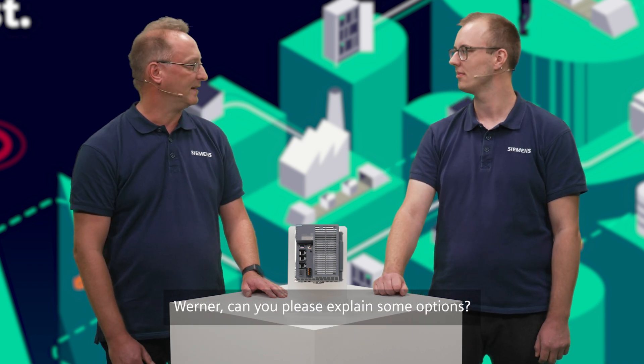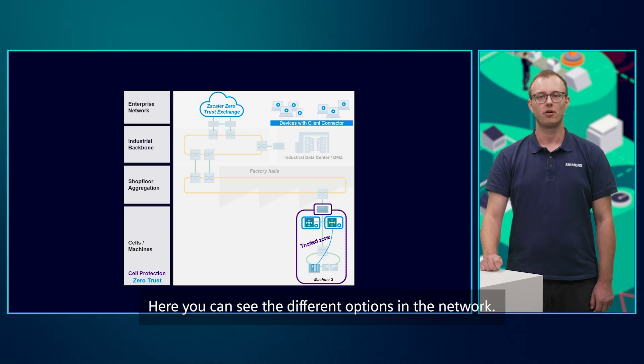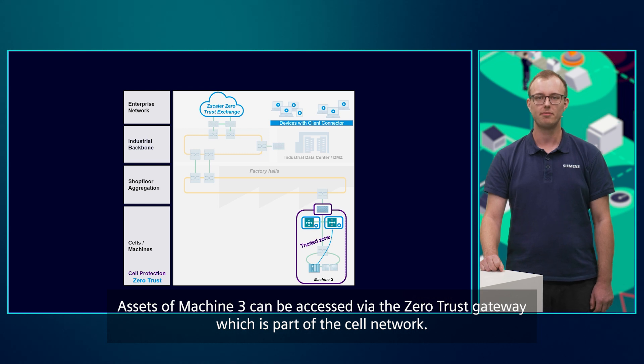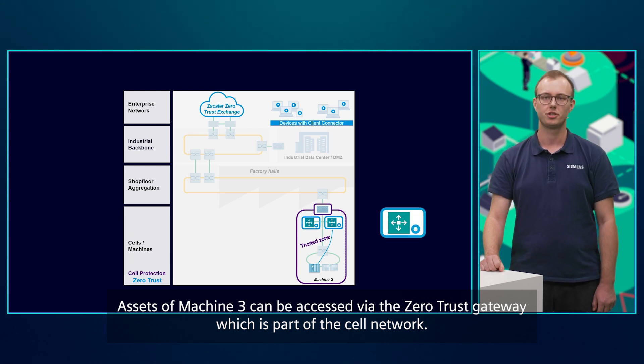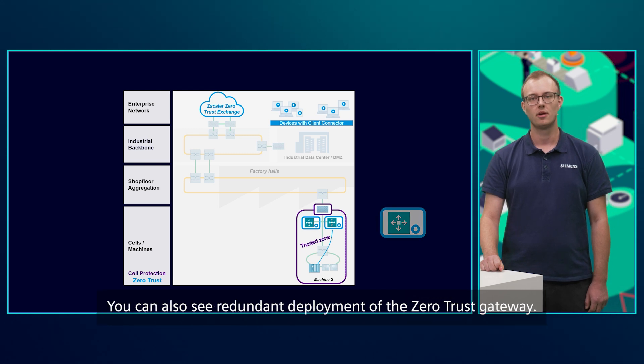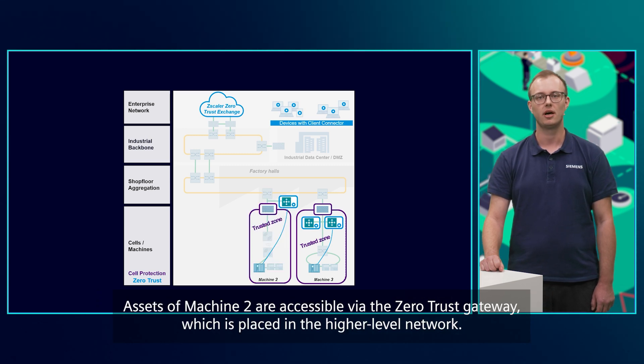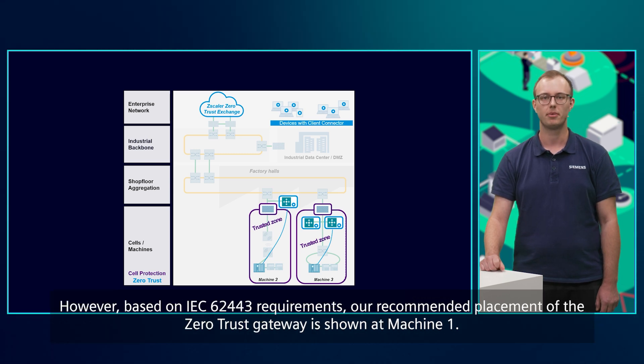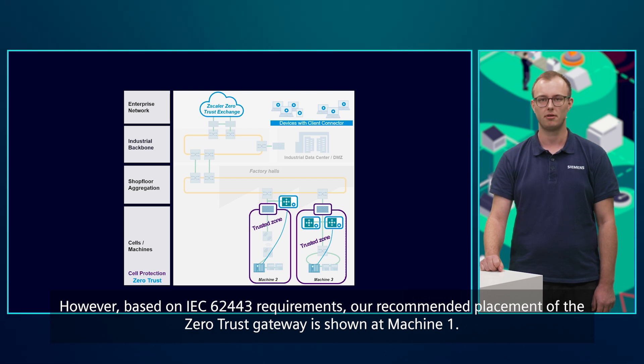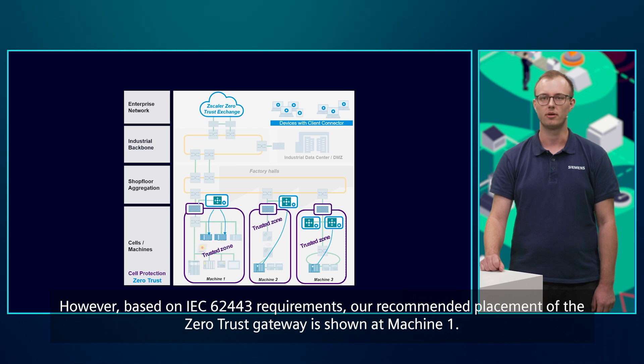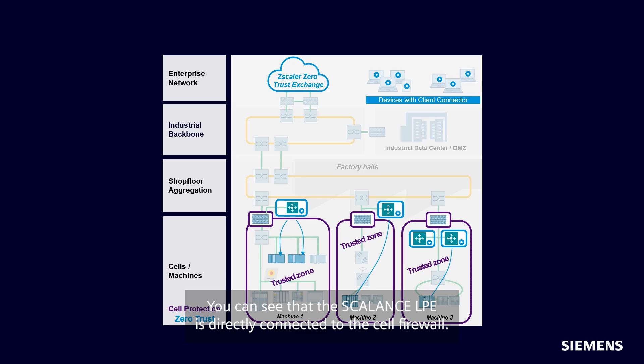Werner, can you please explain some options? Sure. Here you can see the different options in the network. Assets of Machine 3 can be accessed via the Zero Trust Gateway, which is part of the cell network. You can also see redundant deployment of the Zero Trust Gateway. Assets of Machine 2 are accessible via the Zero Trust Gateway, which is placed in the higher-level network. However, based on IEC 62443 requirements, our recommended placement of the Zero Trust Gateway is shown at Machine 1. You can see that the SCALANCE LPE is directly connected to the cell firewall. This allows the creation of a separate subnet, which acts as a cell DMZ.